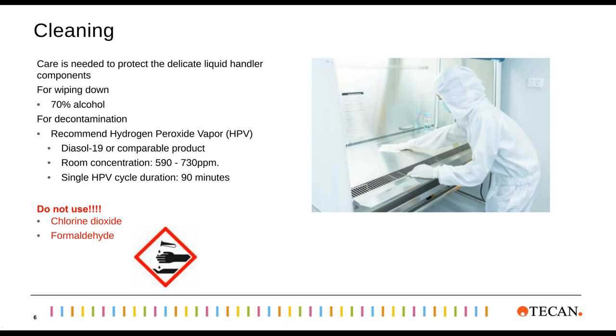Cleaning is another key consideration. With a large, expensive liquid handling instrument inside a hood, you can't just bomb it with formaldehyde like you would do for a regular laminar flow hood with nothing in it. You can wipe down the instruments with something like 70% alcohol. And for our liquid handlers, we recommend hydrogen peroxide vapor.